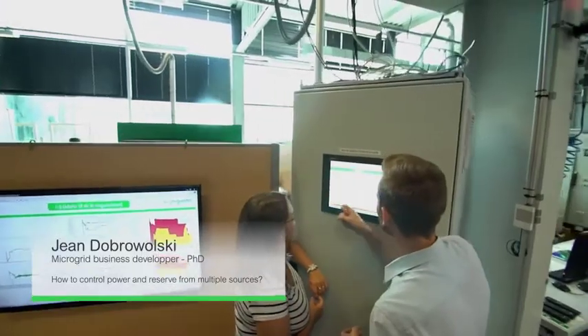To solve these problems, we have developed the virtual synchronous generator inverter, which consists of some renewable power source, some power storage, and a smart inverter that mimics the behavior of real gensets. Even when renewable generation is able to behave as a genset, we still need to coordinate the multiple energy sources in order to ensure the frequency and voltage regulation while maximizing the use of renewable energy. This is the role of the microgrid controller that manages power flows in the entire microgrid, using short-term prediction in order to make decisions about reserves, cope with intermittency, and at the end, boost the use of green energy.